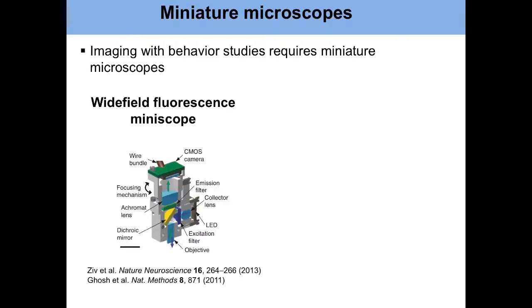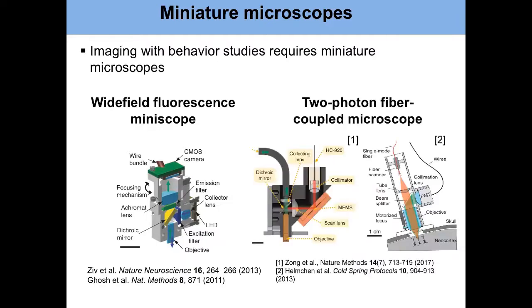Okay, so again, the previous example was using a one photon wide field miniscope, as they're called, and it uses an LED as its light source, a dichroic and some lenses, and images onto a CMOS camera. And this is good in a way, but if you're trying to image deeper in tissue and you want to know detailed structures of what you're seeing, something like two-photon fiber coupled microscopes can be of great benefit.